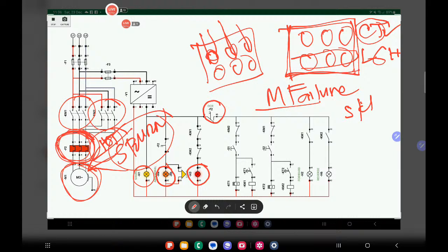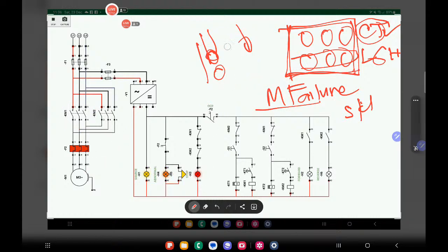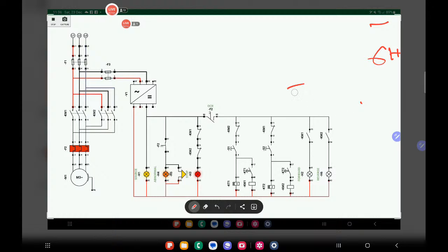Now, single phasing might be happening also on your contactors, right? But of course, the limitation of testing a live circuit will happen here. You cannot test a contactor if it is single phasing in a high load or at any circuit that could compromise the safety of the technicians and your machineries. So the best way to check if the main contactor is giving a single phasing is to switch off the main breaker and try to activate it manually by pushing the magnetic contactor.